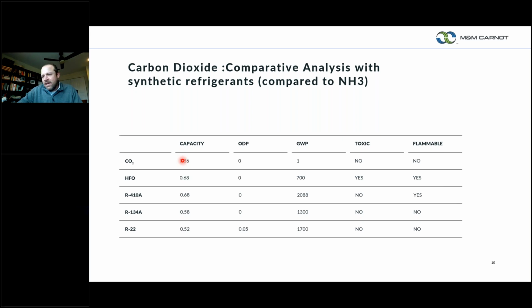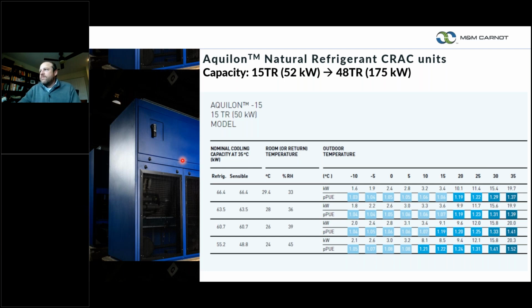But we came up with a design, and a couple of years afterwards it was deployed in one of the first data center rooms for a telecom provider. We had one size, one footprint, and then we were asked to build a different size and another size. So now we have a pretty good catalog of computer room cooling units that will allow you to use CO2 and take up a smaller footprint than what you would see in a synthetic refrigerant type system. The nice thing that I'll talk about is the properties of CO2 as a refrigerant.